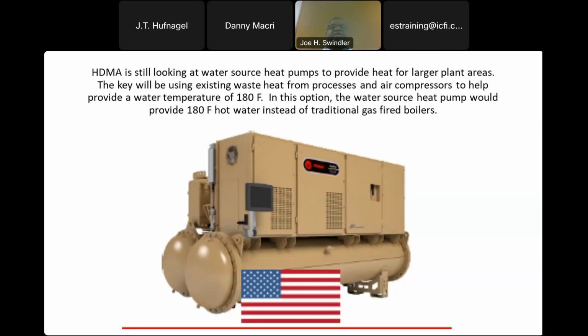So we took a second look. That's our strategy going forward. But for bigger applications, we took a second look at water source heat pumps. And what we decided to do there was, even though the water source heat pump only makes 110 degrees, we could use waste heat from air compressor cooling water, RTO flue gases, etc., and some heat exchangers to help increase the temperature up to 180 degrees. So that's our plan going forward, to use water source and air source heat pumps to make 180 degree water for larger applications.